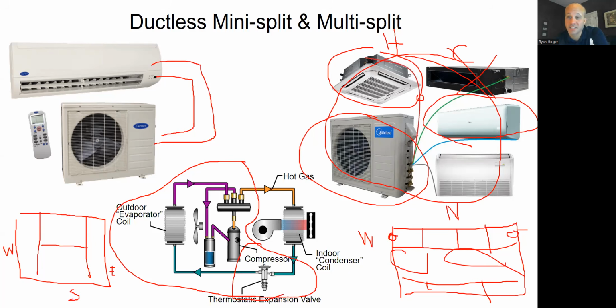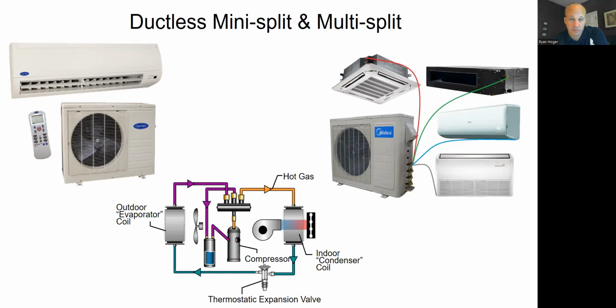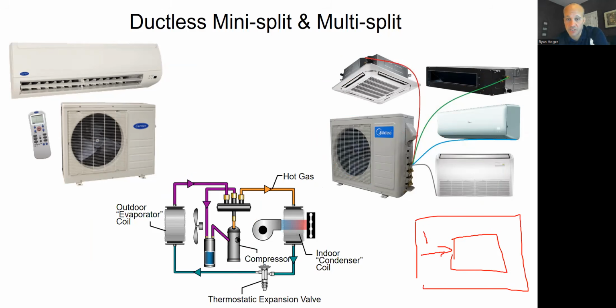And you generally don't want to mix interior and exterior either, right? So I got to clear this off. You don't want to mix interior and exterior either, right? Because on a big enough building, I don't know if we said this on module 1 or not, once I get like, let's say 15 feet from the exterior wall, this is cooling only year round, nonstop, balls out every day, no matter what. I don't put heaters in those spaces. I literally don't put them in. I don't design them in there, right?